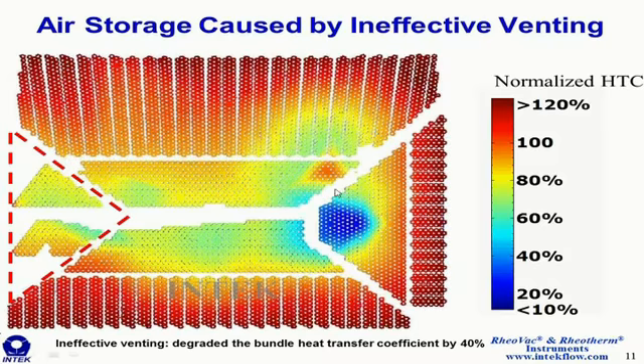And what happens in this condenser is that the venting arrangement is such that in this condition, the vacuum pump capacity is split pretty much evenly between the 2 shells. So 50% coming out of one shell, 50% coming out of the other shell. But a condition arises where one shell will receive, say, 80% of the vacuum equipment capacity, and the bundle in front of you, its venting capacity decreases to about 20%. And so what I'm going to do is animate this bundle as that venting capacity is decreased, and you'll be able to see how the performance profile changes and air storage gets worse in this bundle.